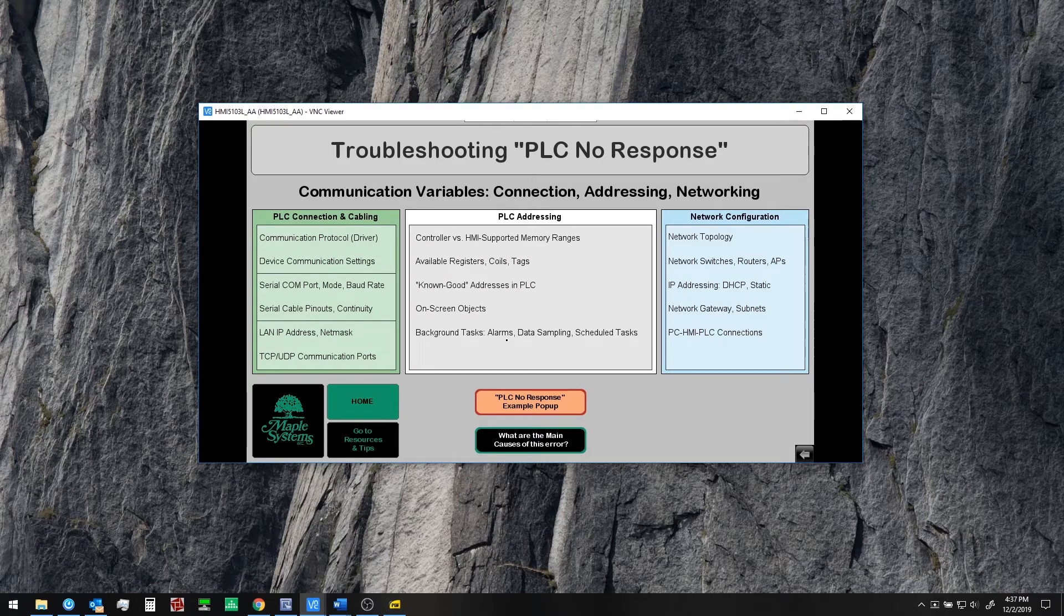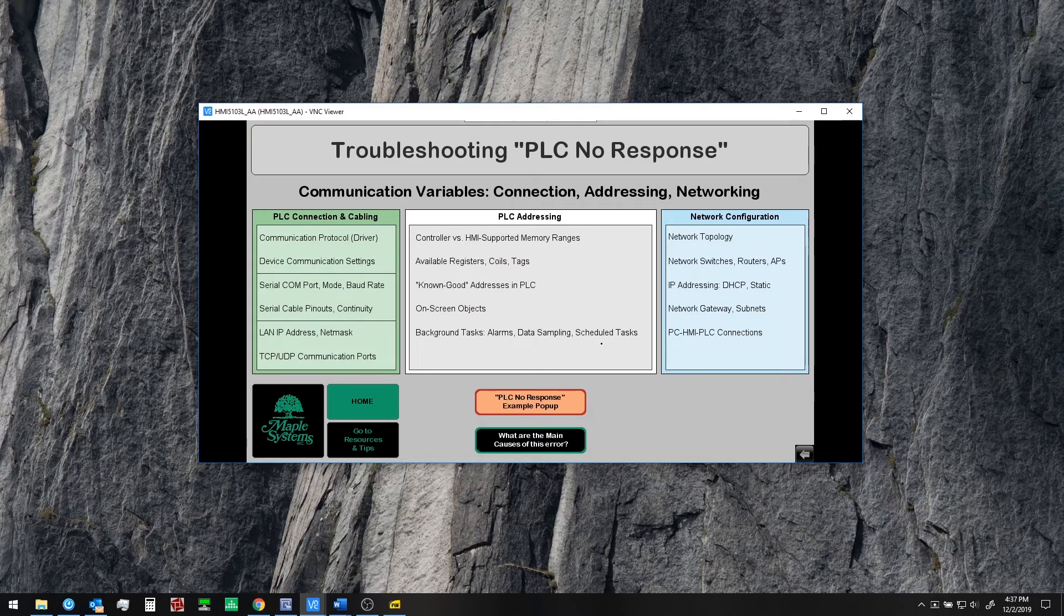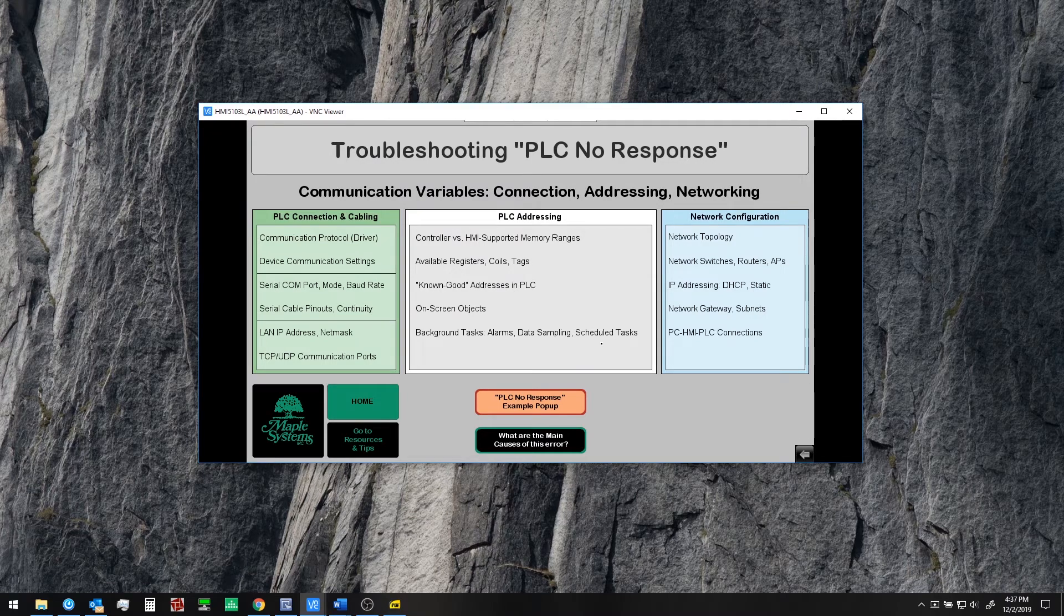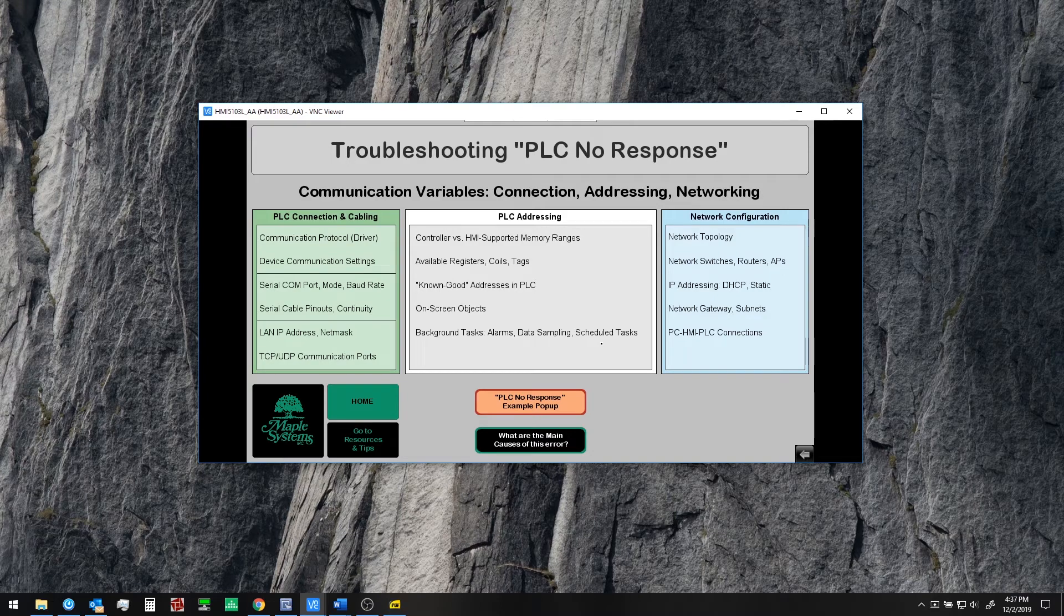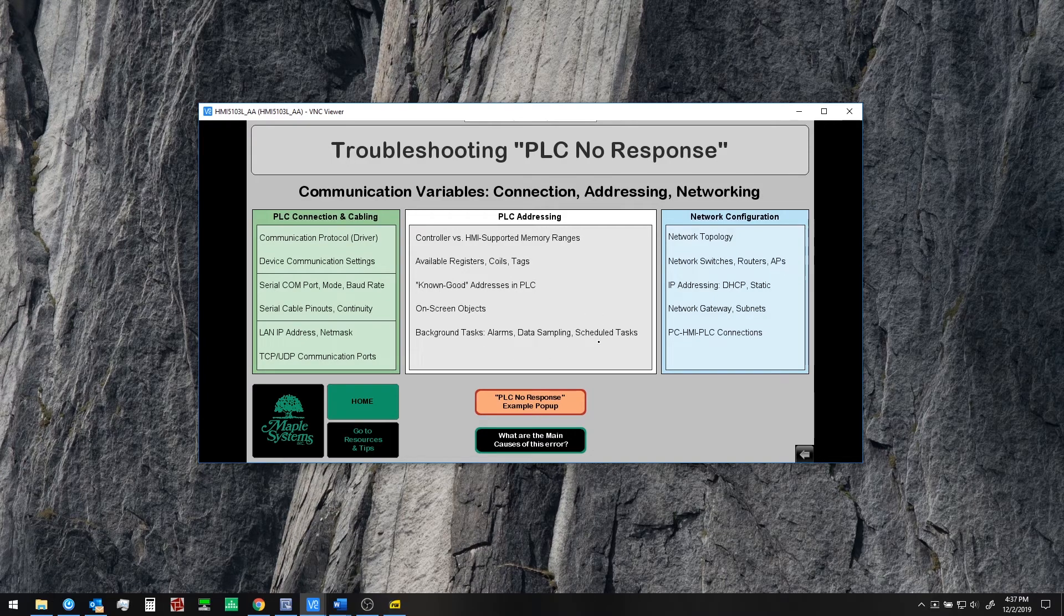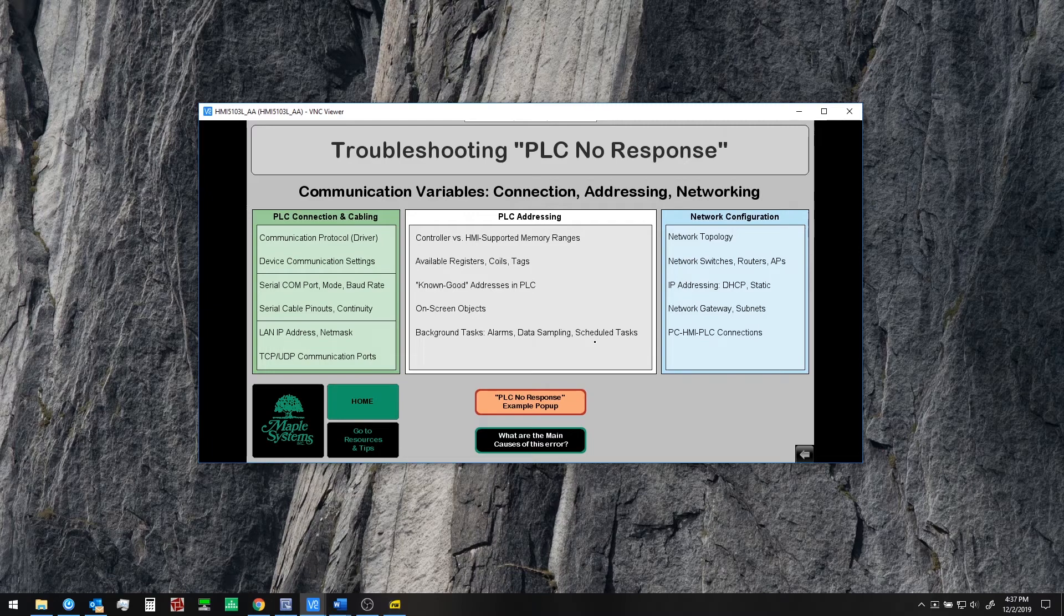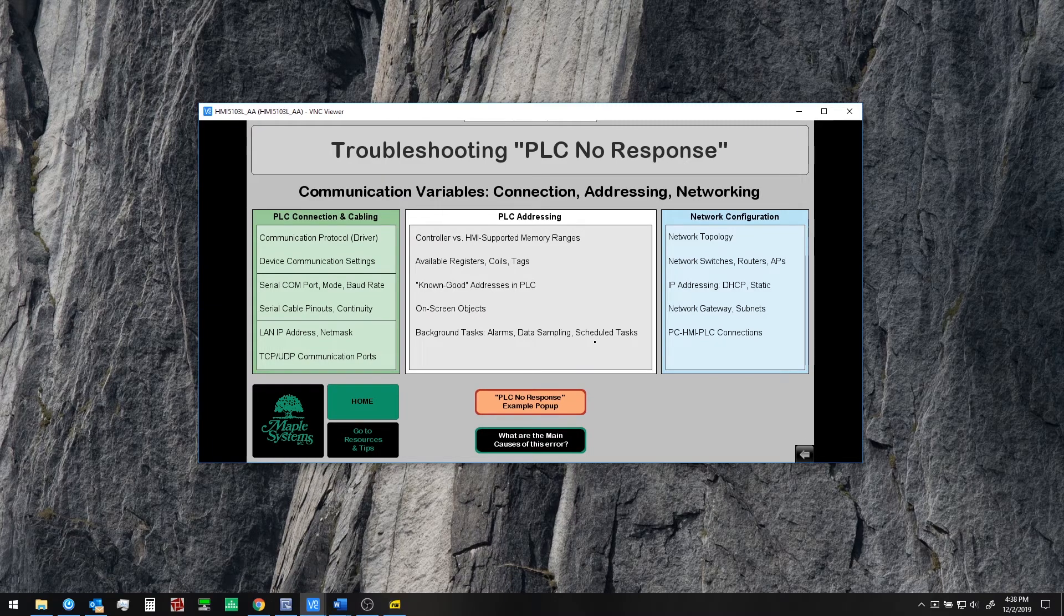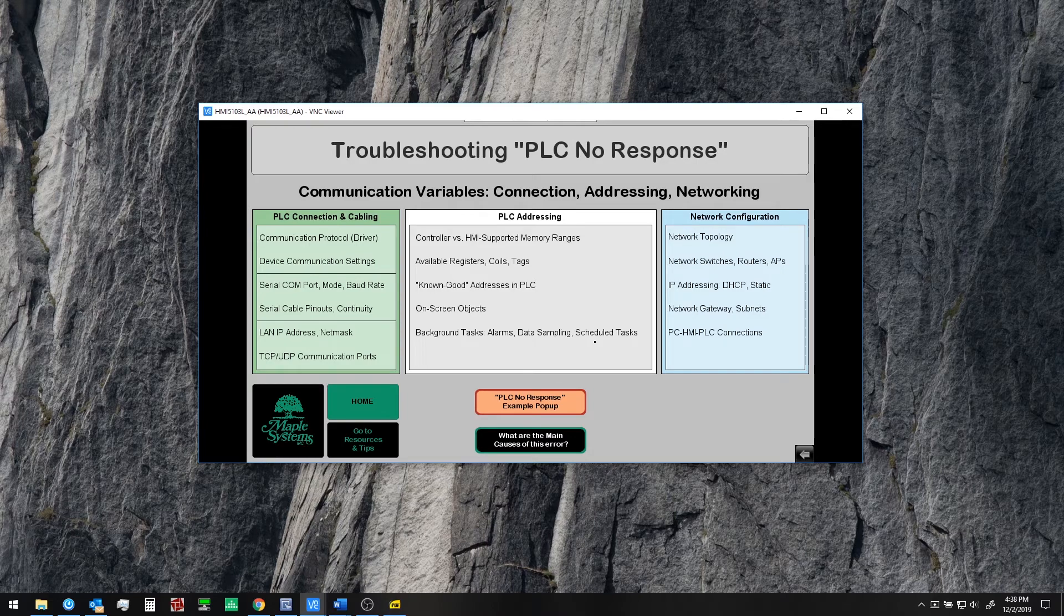Here's one though background tasks which may not have considered yet. So any alarms data sampling or scheduled tasks in your project any macros these can all run in the background regardless of which window showing on the HMI. And so these if they are pointing at an invalid register in the PLC could certainly be causing your issue of PLC no response error messages showing on the screen.